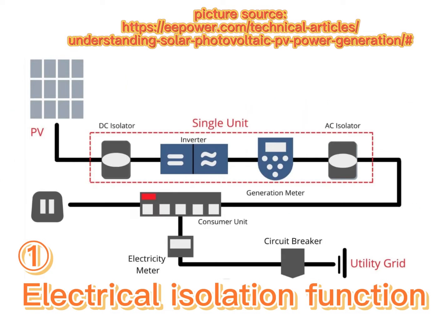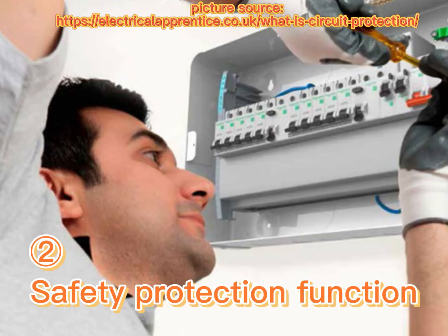1. Electrical isolation function. During installation and maintenance, it cuts off the electrical connection between photovoltaic modules, inverters, power distribution boxes, and the power grid to provide a safe environment for operators. This cutoff is a manual operation. 2. Safety protection function. It provides AC circuit protection in case of overcurrent, overvoltage, short circuit, overtemperature, and leakage current. It can automatically cut off the circuit to protect the safety of people and equipment. This action is realized automatically by the breaker.